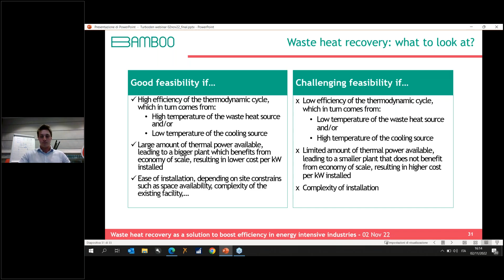So to sum up, the ideal project consists of having the temperature of the heat source above 350, and so our thermal vector above 300 degrees C. Of course, the higher the better, because higher temperature will result in higher efficiency. Then thermal power available from the heat source above 18 to 20 megawatt. This is true for the medium-size plant. Instead, for lower size plants like biomass, typically we can also reach good efficiency with 3,000, 4,000 kilowatt of thermal power available, because in general the temperature of the heat source is much higher than 350, reaching about 700 to 800 degrees C.